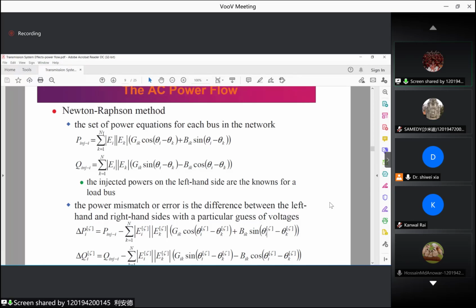To find this power, you take the summation of the voltage at bus I and bus K, and the conductance at bus I K. The real power is equal to the summation from 1 to N of voltage I times voltage K, times conductance IK cosine of the phase angle at bus I minus phase angle at bus K, plus susceptance of bus I and K times sine of the phase angle difference between bus I and bus K.